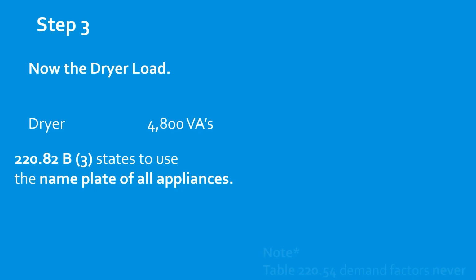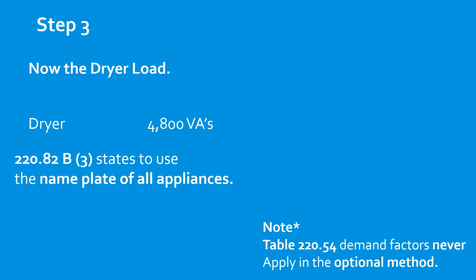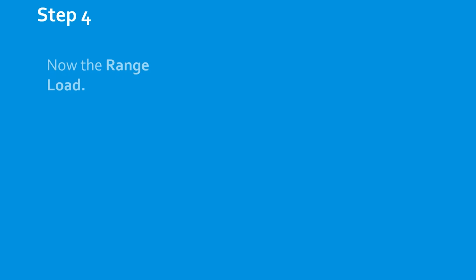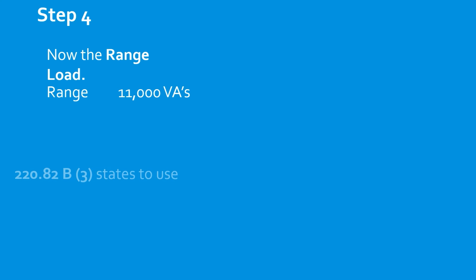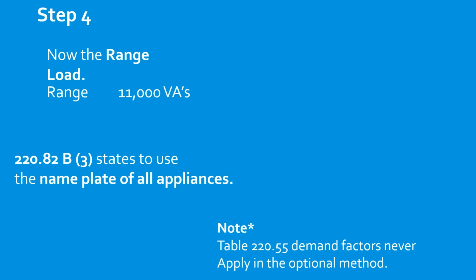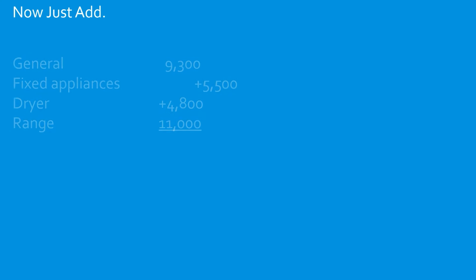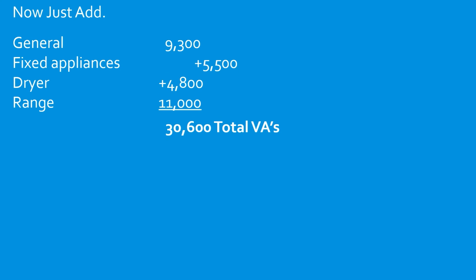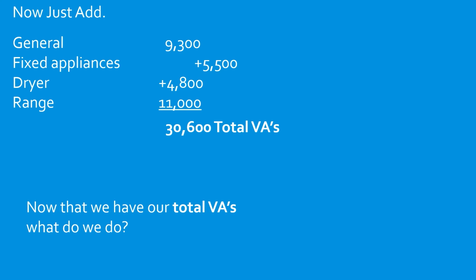Okay, now let's do the dryer. We just use the nameplate. I do want to note that you'll never use table 220.54, the dryer table, for demand factors when doing the optional method. Now let's do the range. 11,000 VAs. We're just going to use the nameplate, and we're never going to use table 220.55, which is the range table, when we're doing the optional method. Okay, now we just add them all together. 30,600 total VAs. Now, what do we do anytime we have our total VAs?